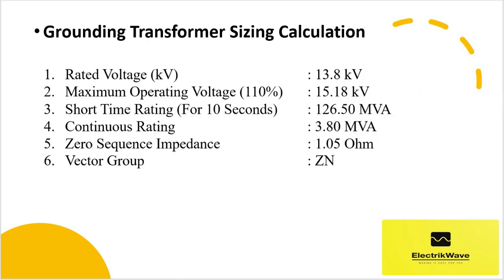We will now do the grounding transformer sizing calculation for the following given parameters: rated voltage 13.8 kV, maximum operating voltage 110% — 15.18 kV, short time rating for 10 seconds: 126.50 MVA, continuous rating: 3.80 MVA, zero sequence impedance: 1.05 ohm, vector group: ZN.